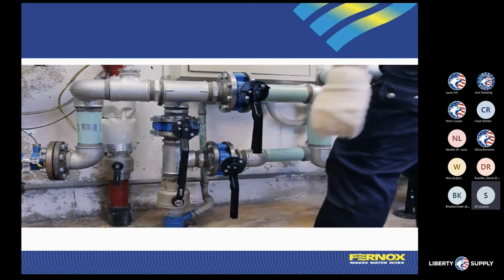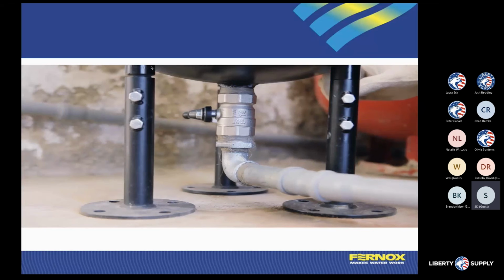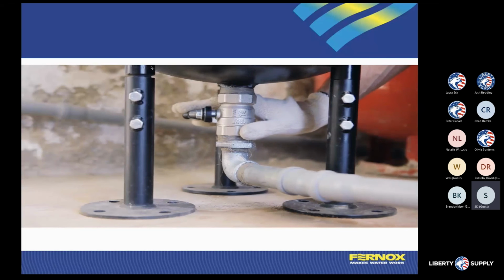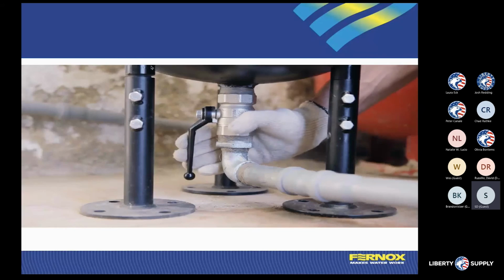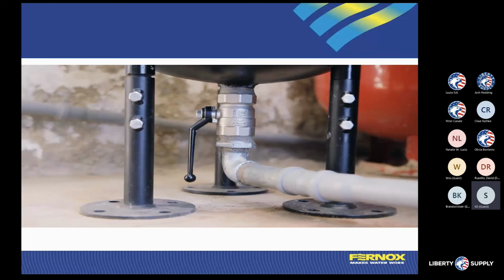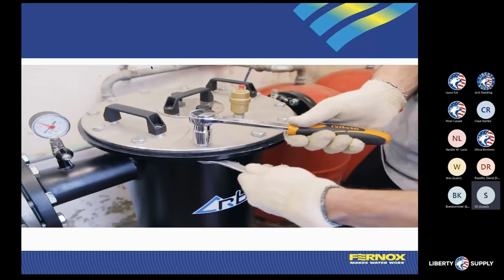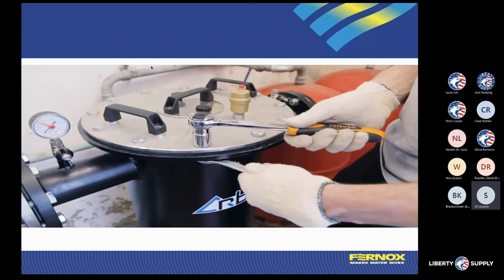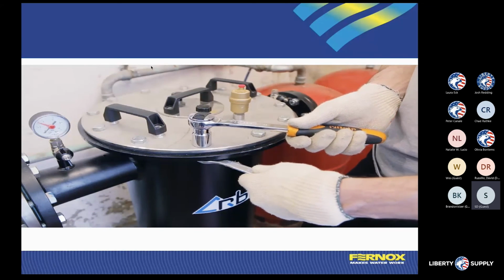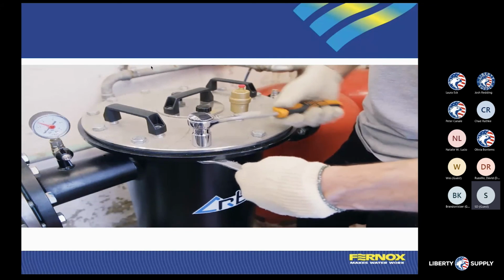What you're looking at here, I believe, is our 2 or 3 inch model. At the bottom we have a drain port, so we're going to flush all the water out of the system. All magnetic filters have some way to have the system taken apart so that you can, A, inspect, and B, clean that system out.